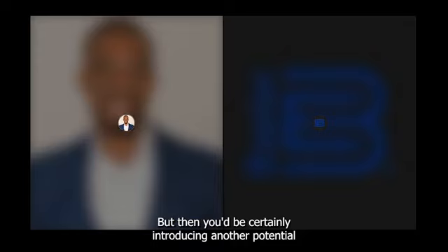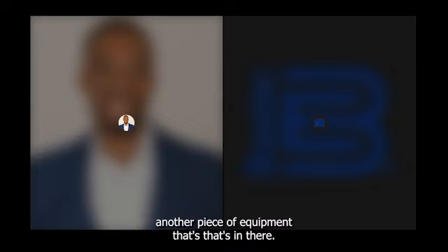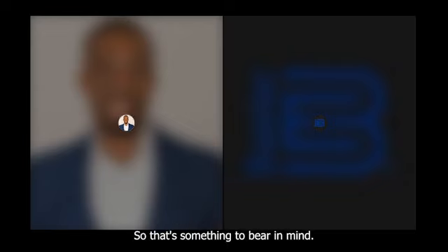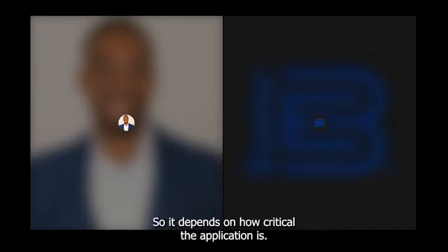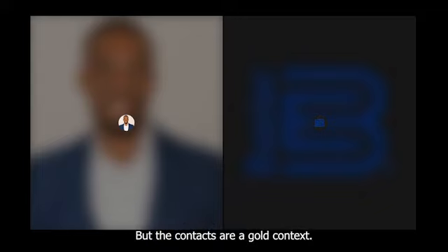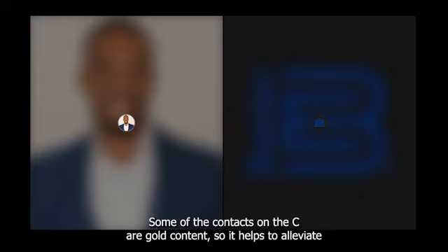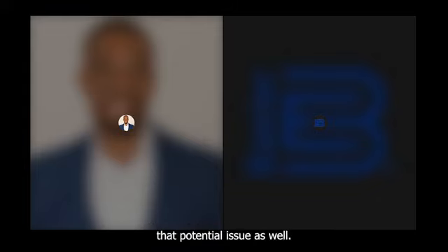But then you'd be introducing another potential point of, well, I don't want to say a point of failure, but it's just another node, another piece of equipment in there. So that's something to bear in mind. And the contact closing times are different for the CEMs versus the controller itself. It depends on how critical the application is, but some of the contacts in the CEM are gold contacts, so that helps to alleviate that potential issue as well.